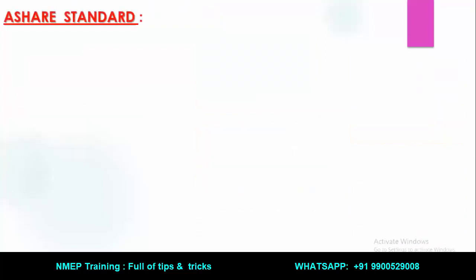Next, very quickly, I will move to the ASHRAE standard. As per ASHRAE standard, you have to maintain the temperature at 25 degrees Celsius or 77 degrees Fahrenheit. And relative humidity should be maintained in the range of 30% to 60%, with 50% being the general midpoint of that range.